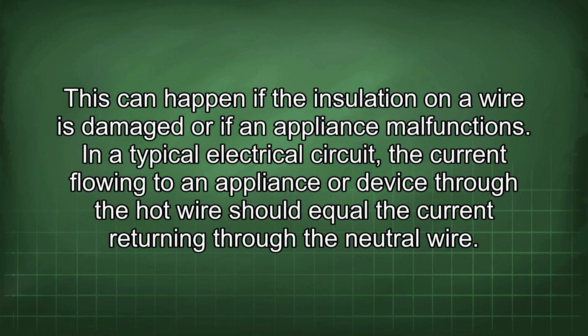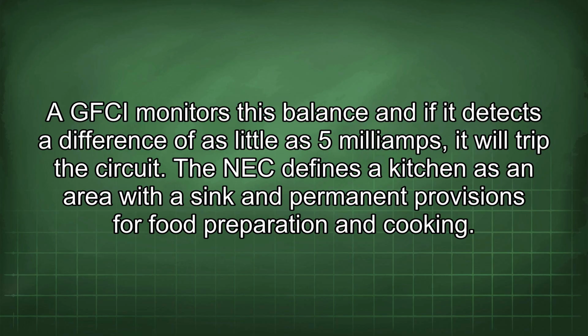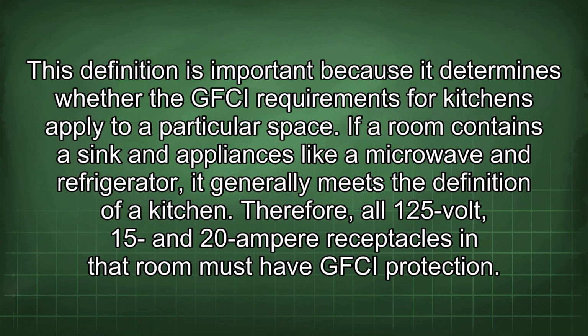In a typical electrical circuit, the current flowing to an appliance or device through the hot wire should equal the current returning through the neutral wire. A GFCI monitors this balance, and if it detects a difference of as little as 5 mA, it will trip the circuit. The NEC defines a kitchen as an area with a sink and permanent provisions for food preparation and cooking. This definition is important because it determines whether the GFCI requirements for kitchens apply to a particular space.